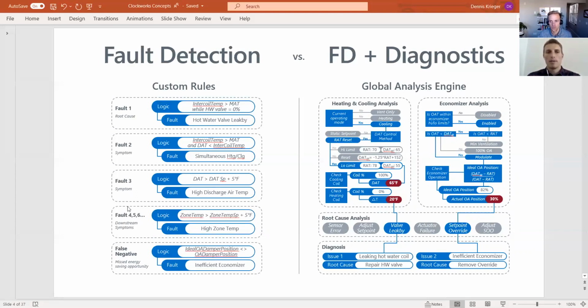Going top to bottom, you might identify that you have a hot water valve that's leaking and shouldn't be, costing you money and energy waste. But you also might be detecting symptoms of that leaking hot water valve, and those rules don't know they're not the root cause, so they present just like the root cause does. You might trigger a hot water valve leak-by fault, a simultaneous heating and cooling fault, and a high discharge air temperature fault. All three of these issues are related - it's one air handling unit, and these are all essentially symptoms of the single root cause: the leaking hot water valve. Such a powerful example.